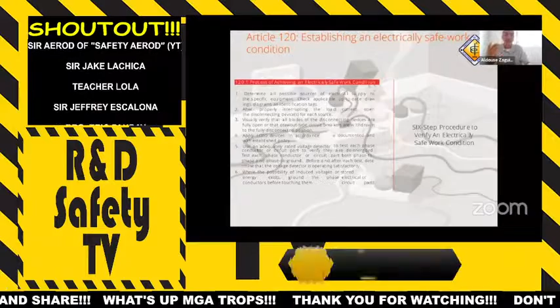Lastly, you ground—connecting the three phases, the three lines, to ground. This is so that if, accidentally, someone turns the breaker back on while a person is working there, it's not the person who gets electrocuted. All of the energy and current will now be directed to earth or ground because of your grounding device, giving additional protection to the person.